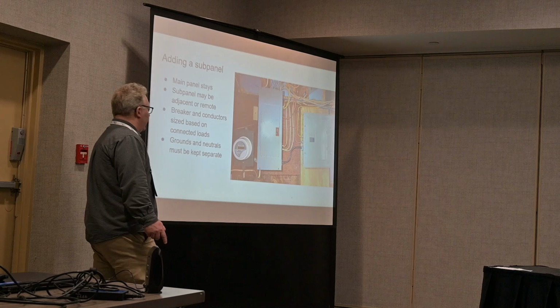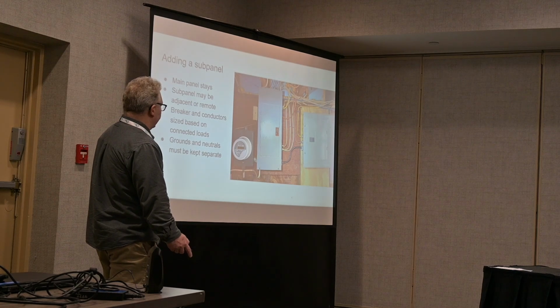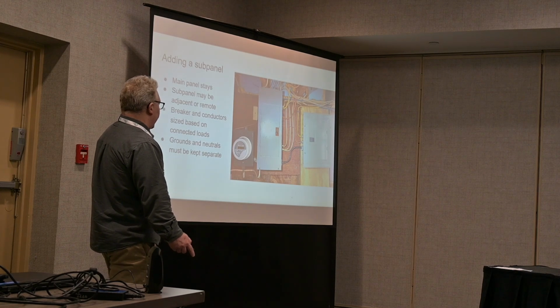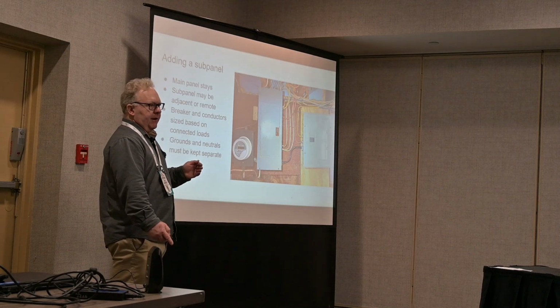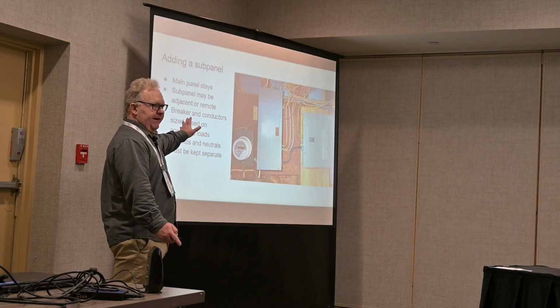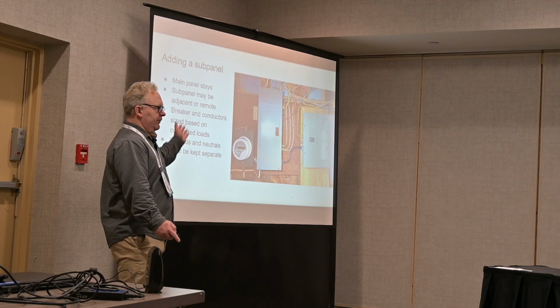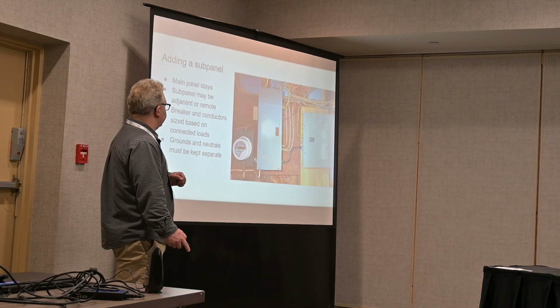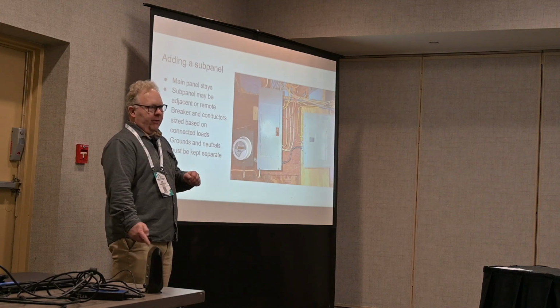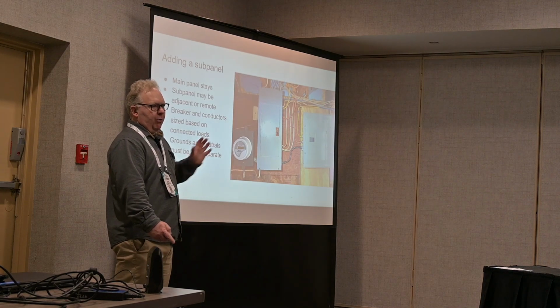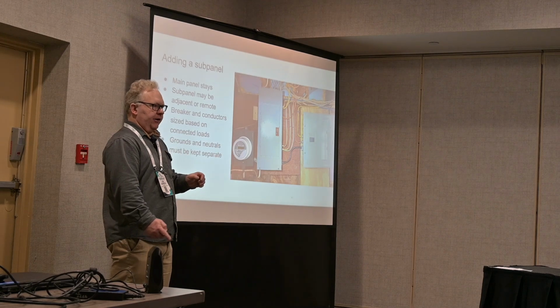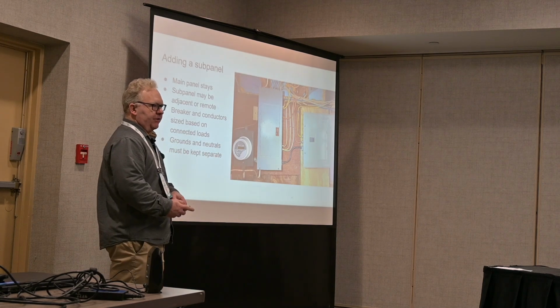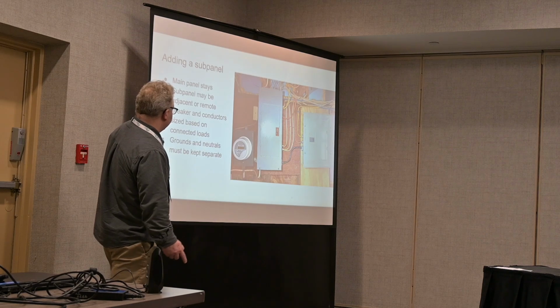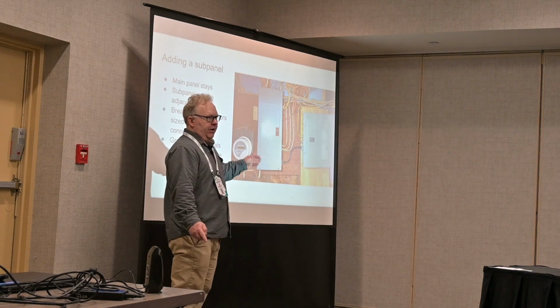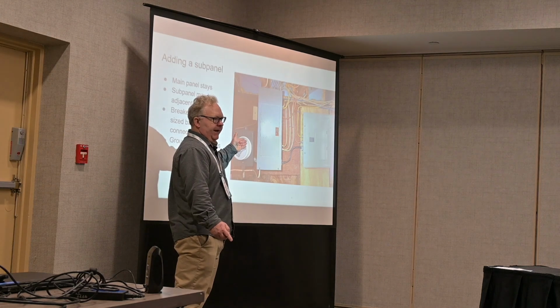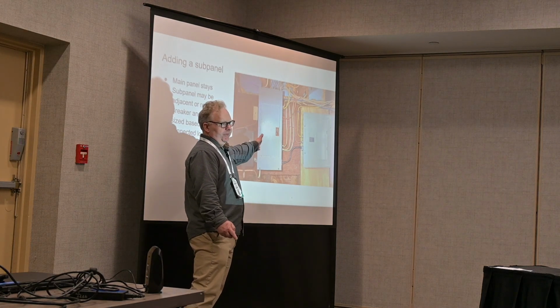Sub panels are often a good option when you just need more spaces. Sometimes the sub panel can be right next to the main panel. It could be closer to the actual end use. So I've seen sub panels put out where 2 heat pumps are going to be installed, and that sub panel serves both those heat pumps. In some cases, you can put in a new 200 amp main panel, and then your old main panel becomes a sub panel of that.